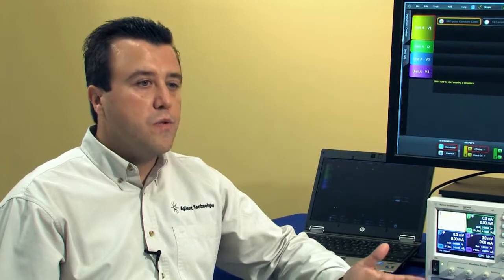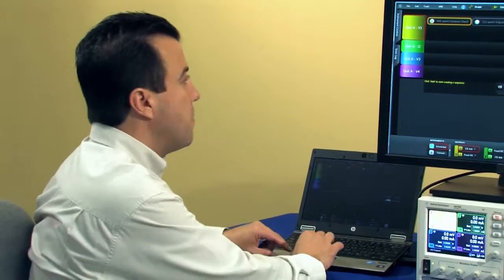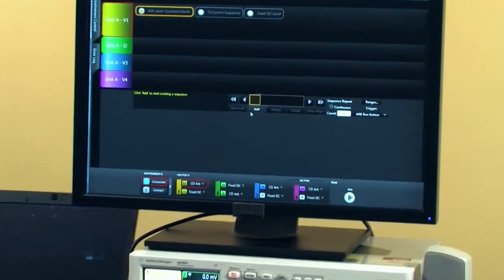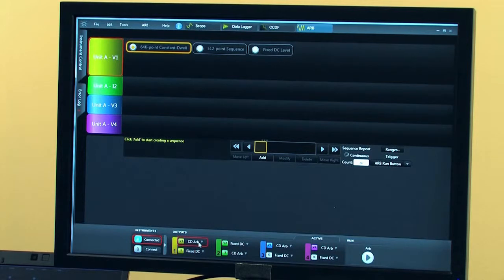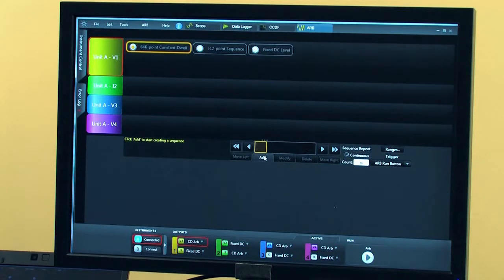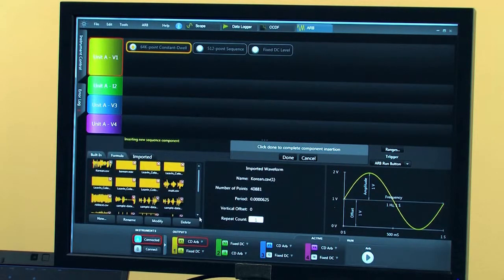One way is we import a WAV file that we recorded and use freeware software to convert the file into a CSV format. I already have the file formatted, and let me show you how I import that through the software. I have channel 1, which is the N6784 module, and I'm going to be adding a 64,000 point arbitrary file. So I'm going to import the file that I had converted to a CSV.